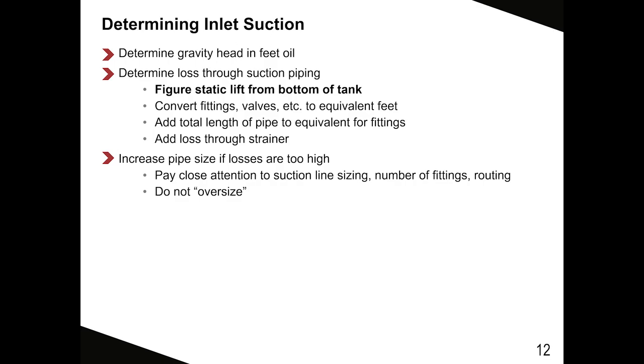As John says, it really is critical to pay attention to the suction pipe sizing. It's critical to the system operation. And typically, I like to see the velocity in the pipe somewhere around 2 feet per second or less.